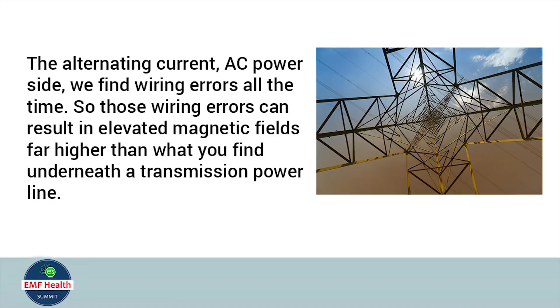But on the alternating current AC power side, we find wiring errors all the time. Those wiring errors can result in elevated magnetic fields far higher than what you find underneath a transmission power line. We always get calls from people who are moving in, or about to buy or rent a place that's underneath a power line or near a utility substation. But in reality, statistically, they're much more likely to have elevated magnetic fields from an internal wiring error.